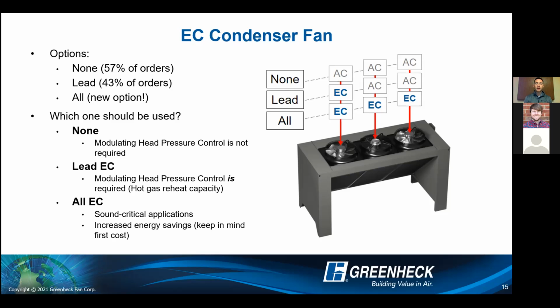And then moving a little further, if we go into all EC motors, that would really be for a couple different reasons. First off is if you have really sound critical applications, the additional condensing fans being EC motor driven will give you the ability to modulate all of them at once, which again, obviously gives you some additional sound reduction. And then also you do get some increased energy savings for the same reason, but you do have to keep in mind the first cost of those additional EC motors is quite substantial. So that is something to keep in mind when deciding whether or not you want lead EC or all EC. So it's really determining what is the purpose and why do you need it.